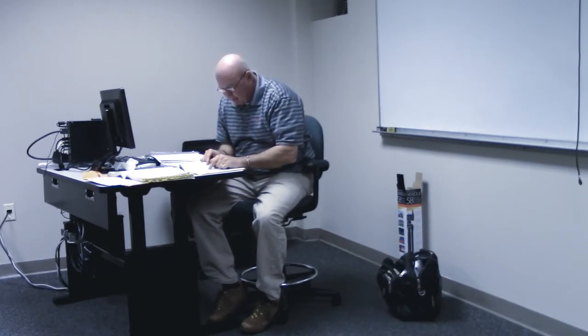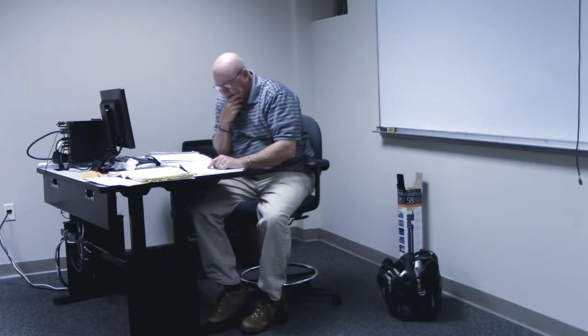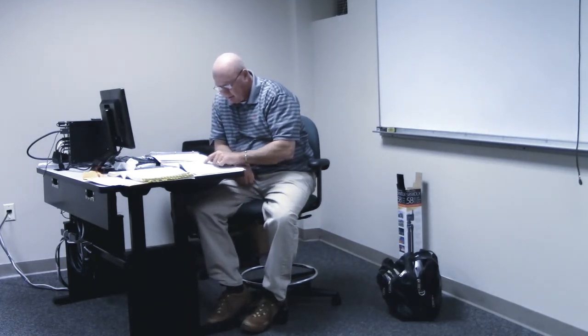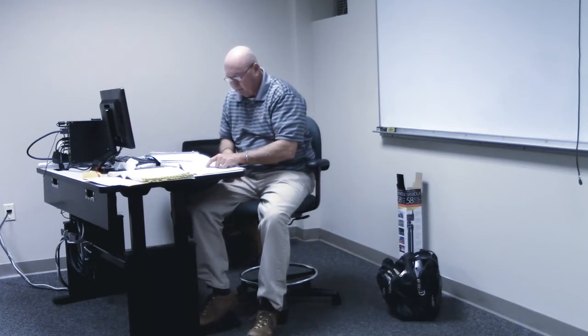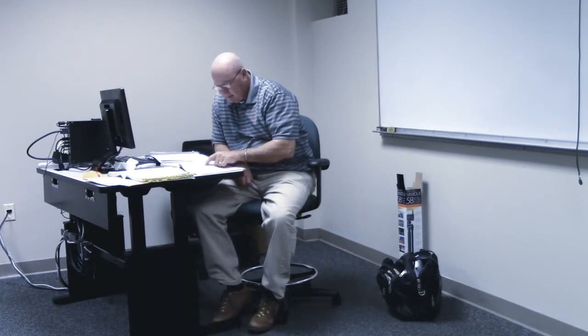Let's look at normal. I'm reading the second paragraph under essential. The EES is divided into equipment branch and life safety and critical branch. The equipment branch consists of those items that are needed to operate the facility but are not directly related to patient care, such as... so that's actually a telephone system is equipment branch. The life safety branch and critical branch consist of those items that are essential to patient care.